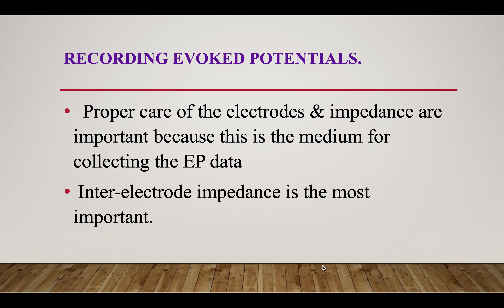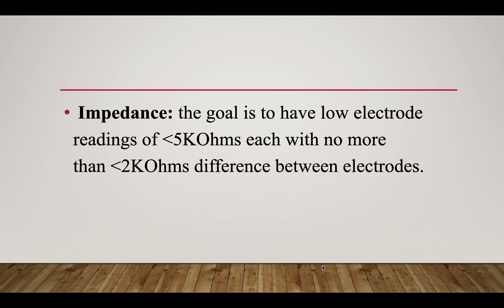When recording evoked potentials, proper care of the electrodes and impedance are important because this is the medium for collection of evoked potential data. Inter-electrode impedance is the most important. The goal is to have low electrode recording of less than 5 kilo-ohms each, with no more than 2 kilo-ohms difference between electrodes.